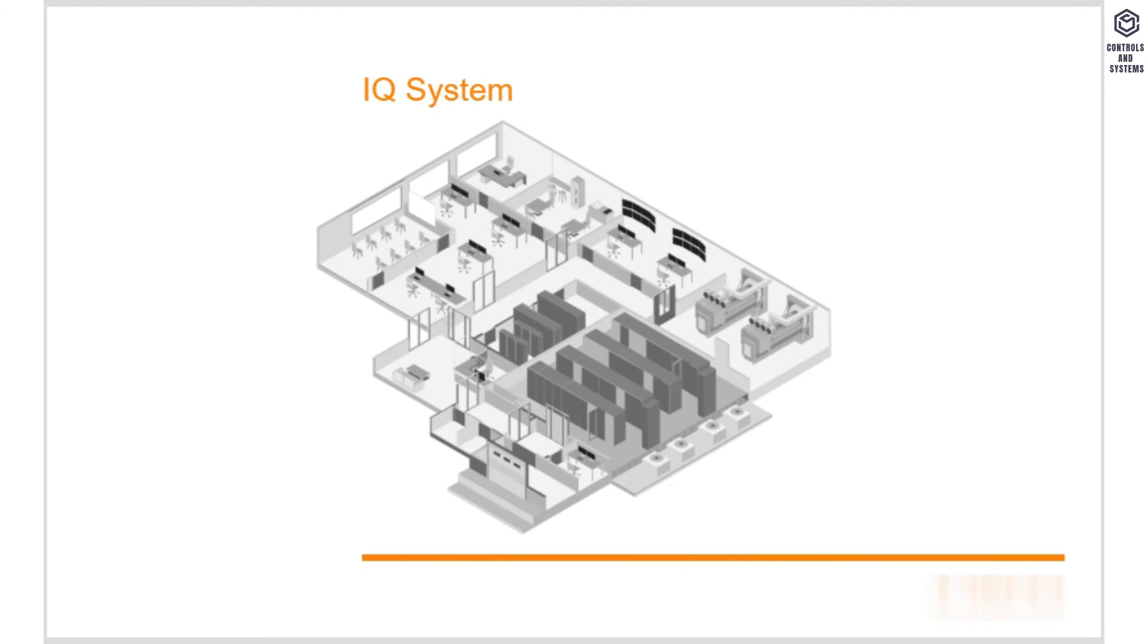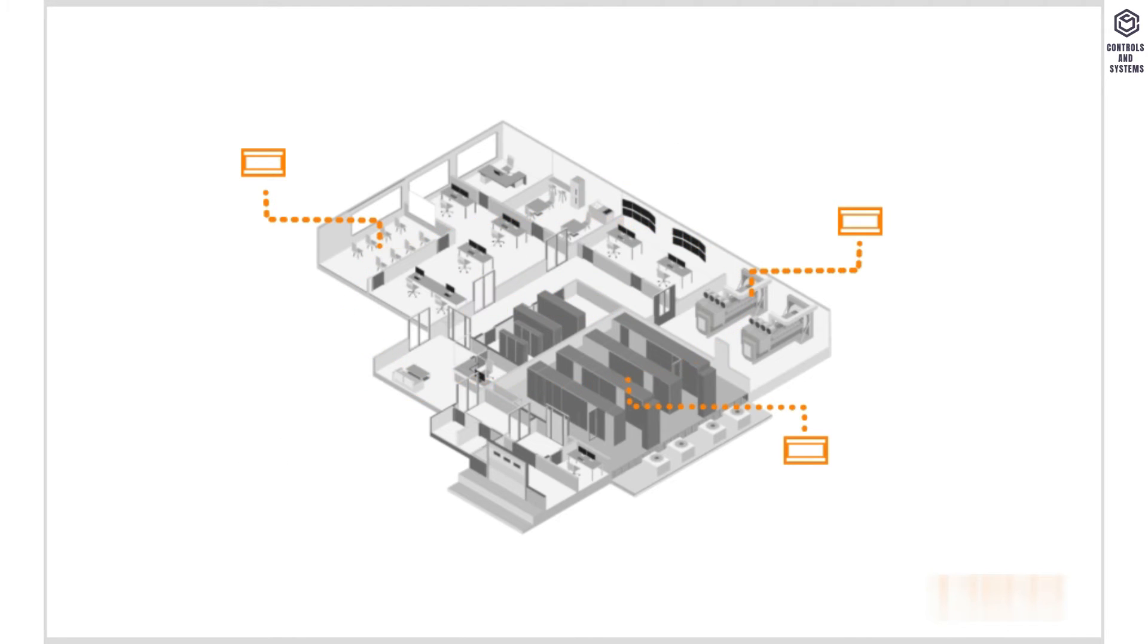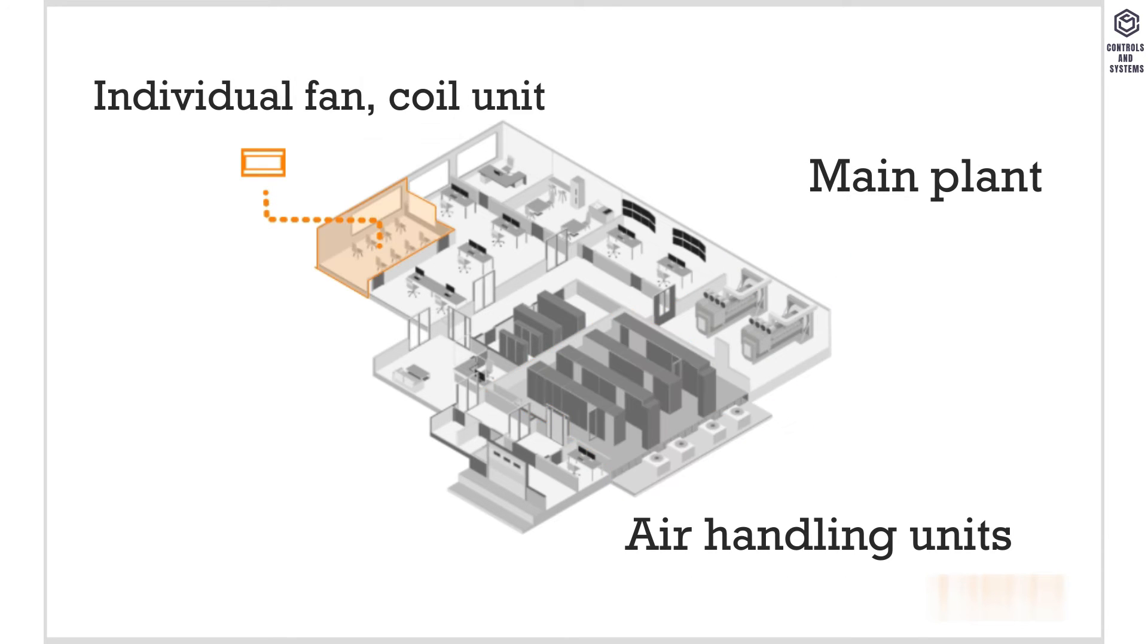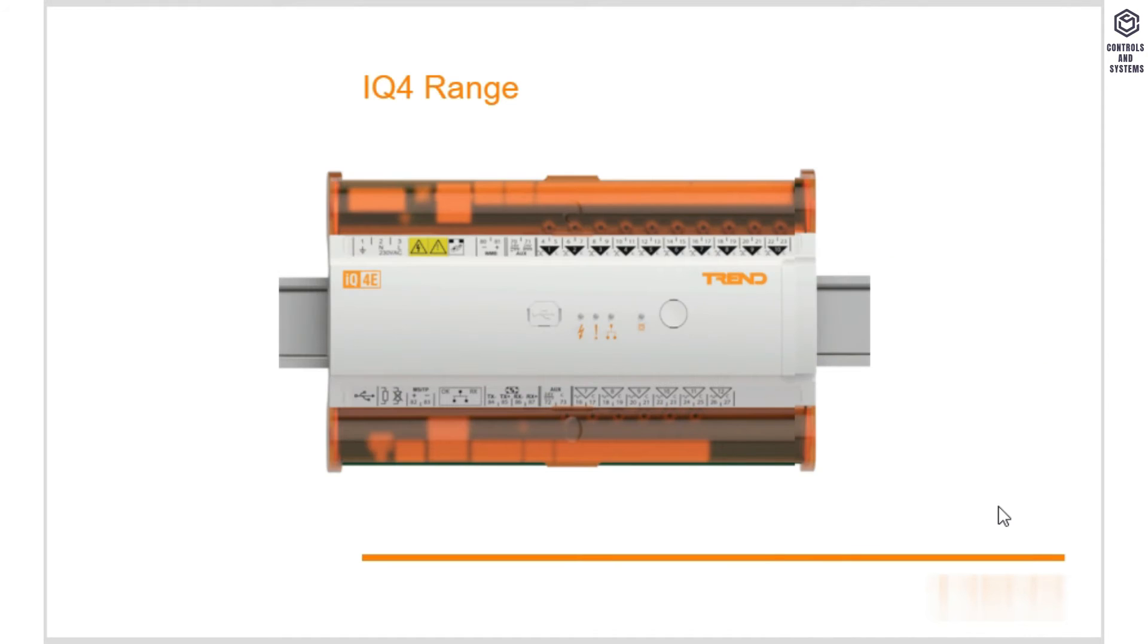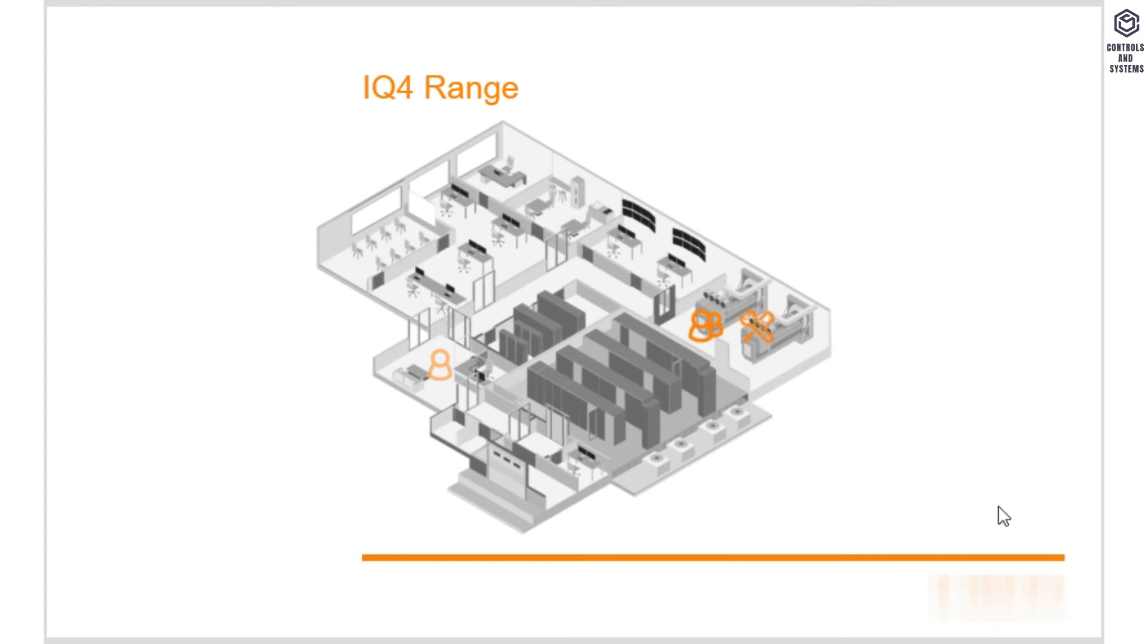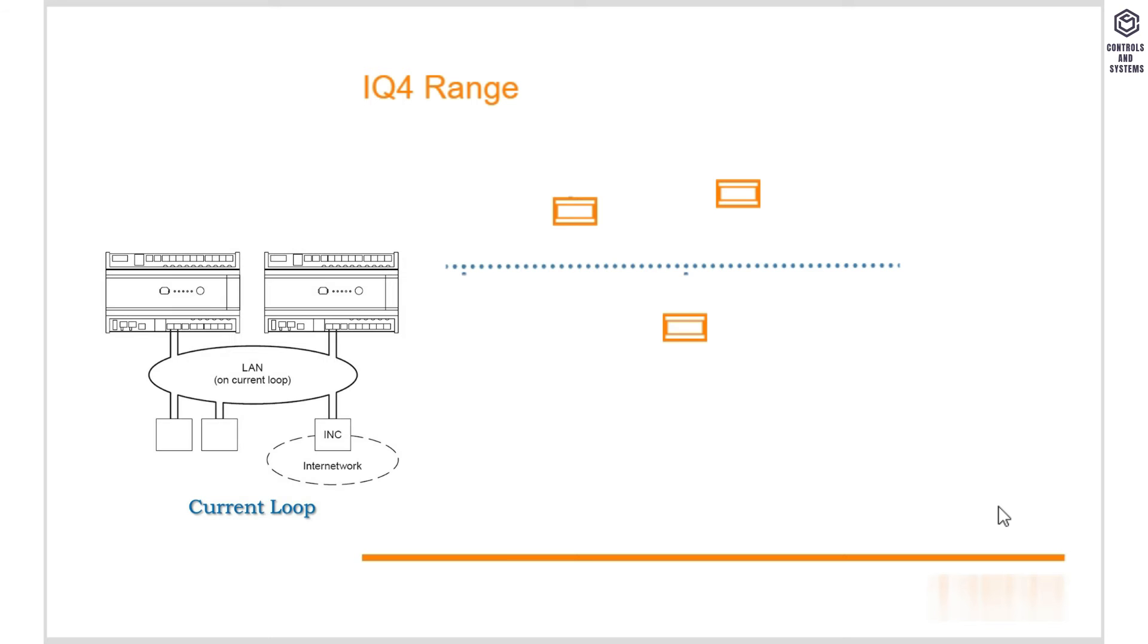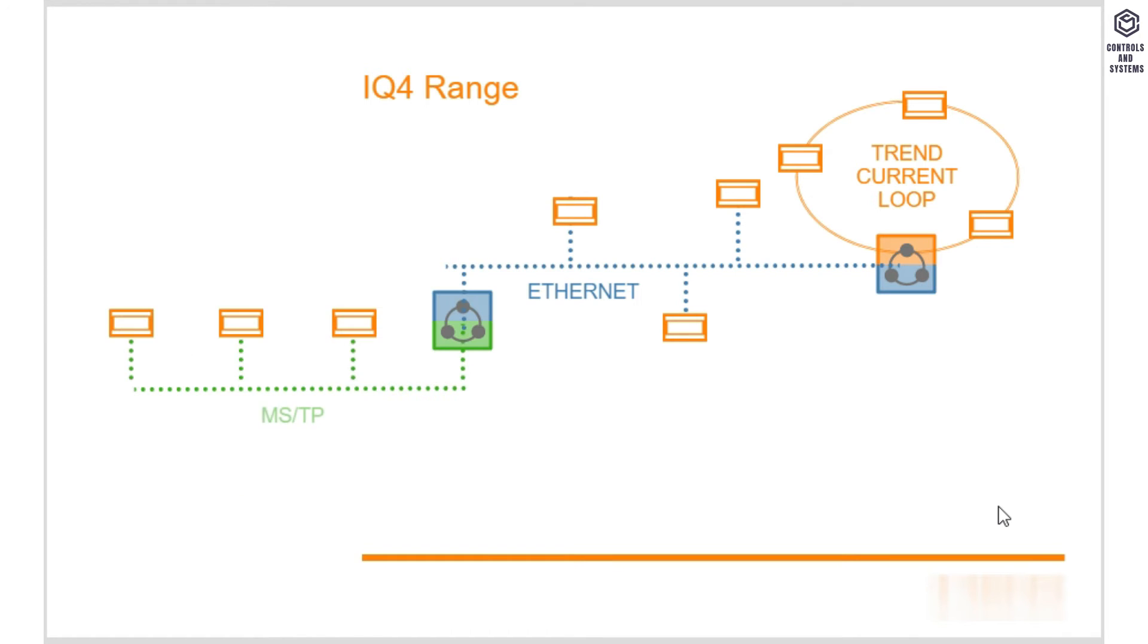The IQ system uses controllers that are distributed across the network. Controllers can be chosen from our range to match the requirements of their role on the site, from controlling main plant or air handling units to an individual fan coil unit within an office. The current Trend controllers are the IQ4 and IQ eco ranges. The IQ4 range is the most flexible of the Trend controllers and can be targeted to desired roles by commissioning teams on site rather than a strategy being installed at the factory. They can communicate with other Trend devices using either Ethernet or Trend Current Loop, with the IQ4NC being able to act as a bridge between those networks and also the MSTP that the IQ eco range uses.